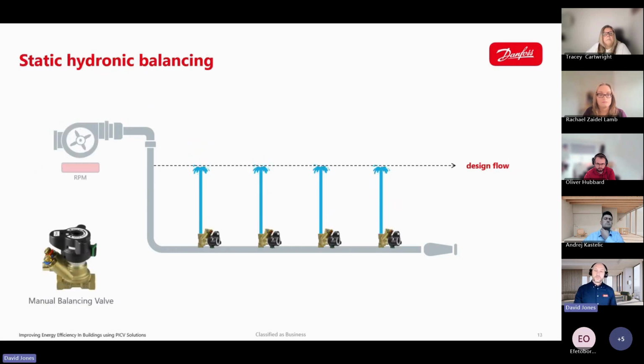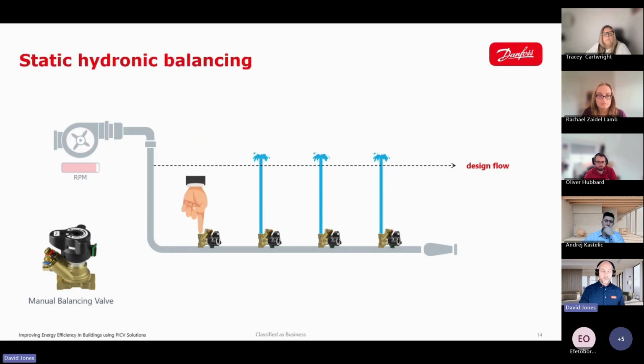So how can we try and balance the flow more effectively? If we look at static hydronic balancing using a manual balancing valve, you can see this is great if we want to balance the flow at full load across each of the outlets. But when one closes off, the remaining 3 receive a greater amount of pressure, although the flow is evenly increased across the remaining 3 outlets. Again, if we close another outlet, we see overflow at partial load at the remaining open outlets. Static hydronic balancing with a manual balancing valve can lead to underflow or starvation phenomena.